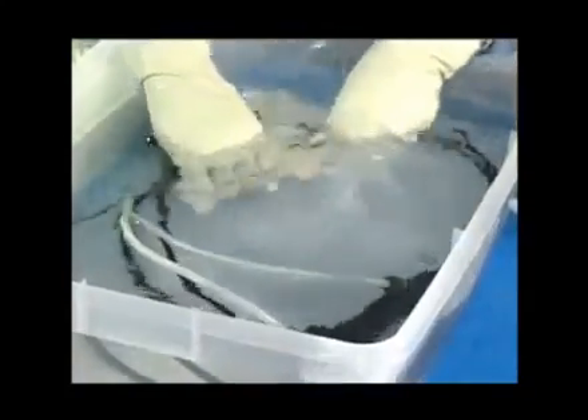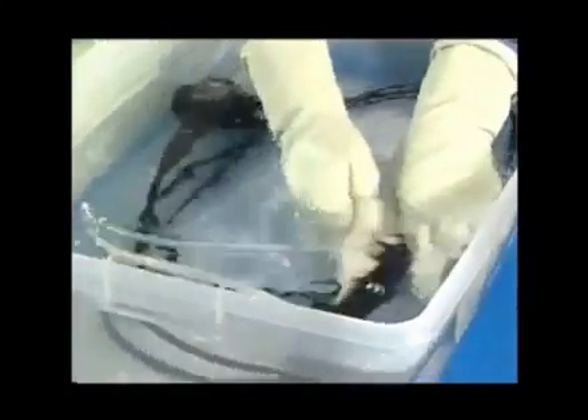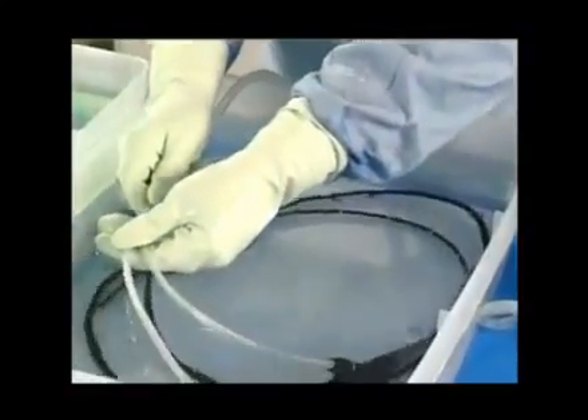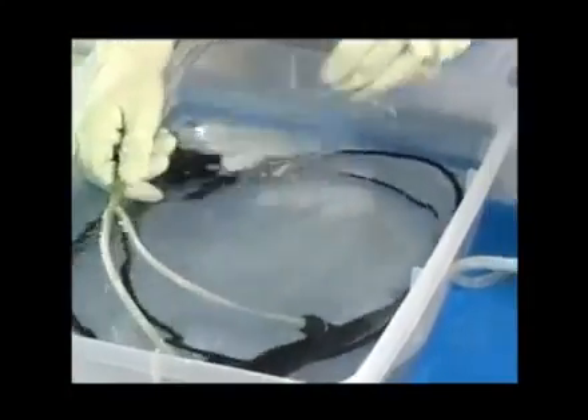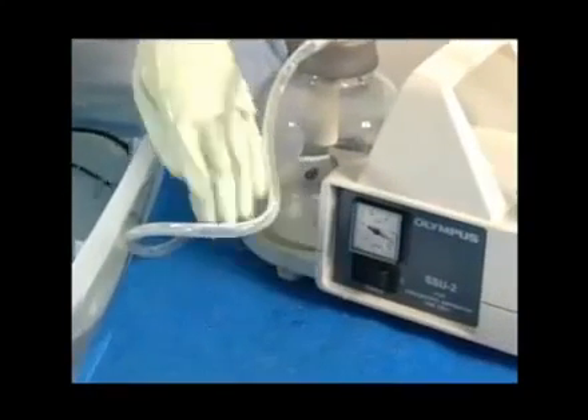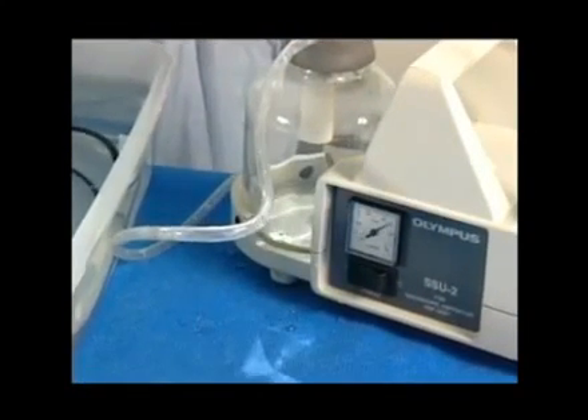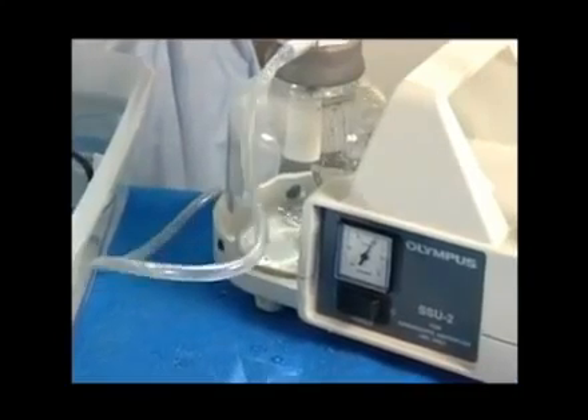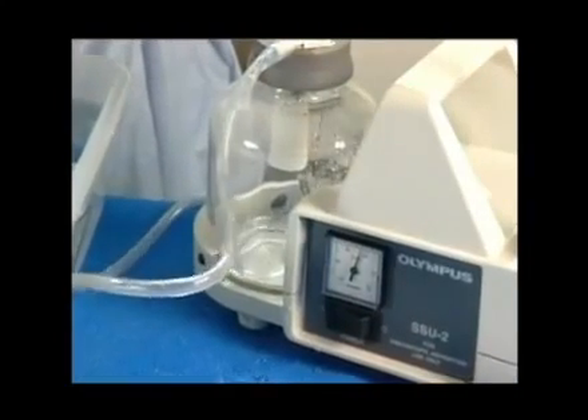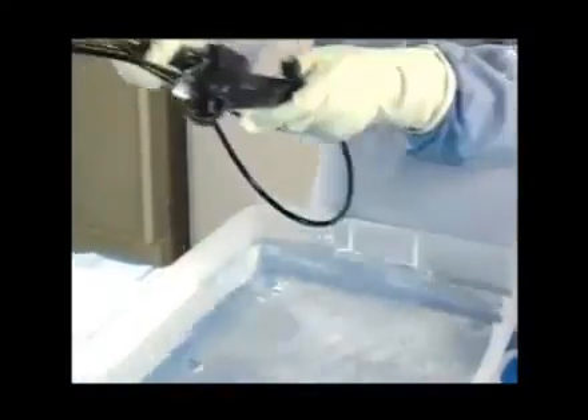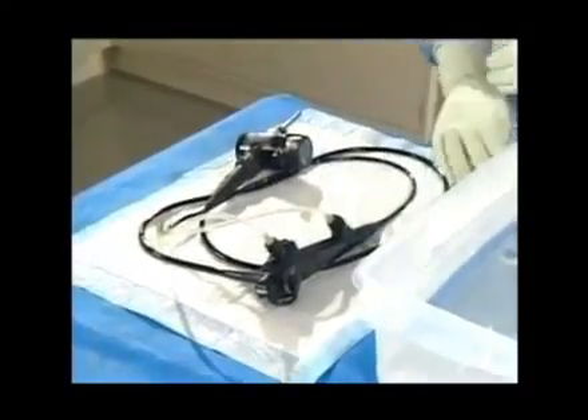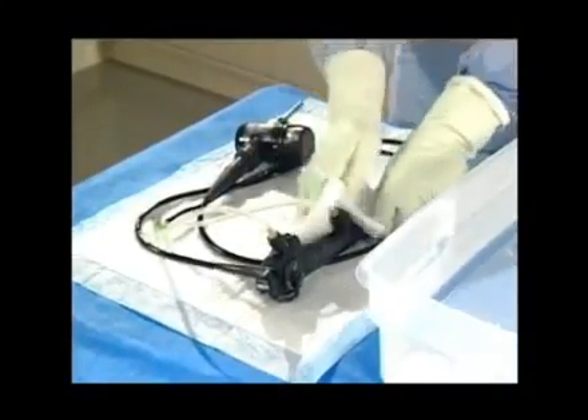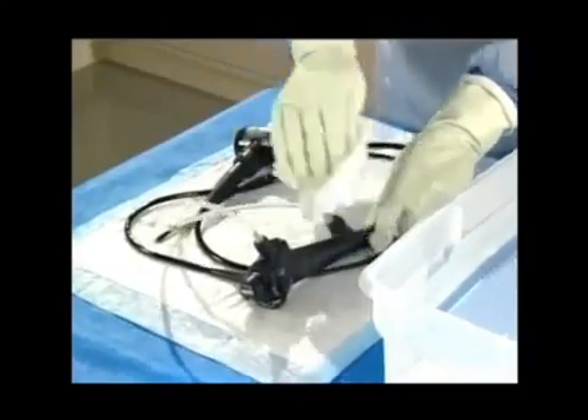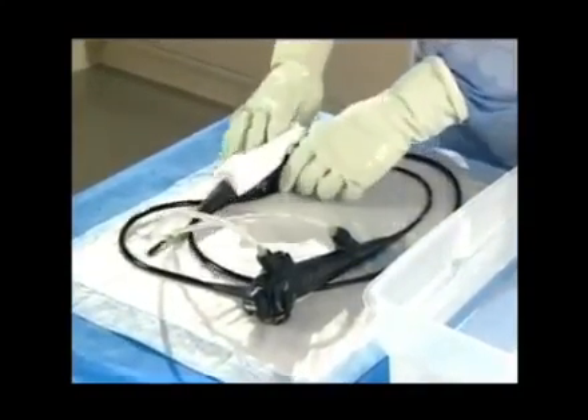With the instrument submerged, use a fresh, sterile, lint-free cloth to thoroughly wipe and rinse all external surfaces. Connect the suction cleaning adapter to a source of suction. Aspirate water through the bronchoscope channels for 30 seconds. Remove the bronchoscope and attachments from the rinse water and place them on a sterile towel. Use a sterile, lint-free cloth to thoroughly dry all external surfaces of the bronchoscope and the suction cleaning adapter.